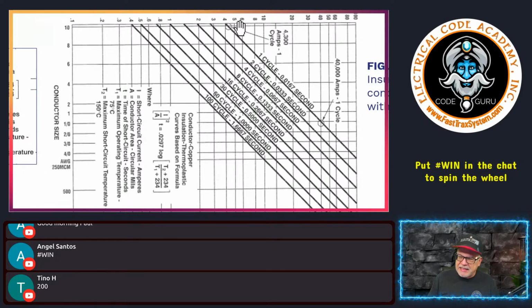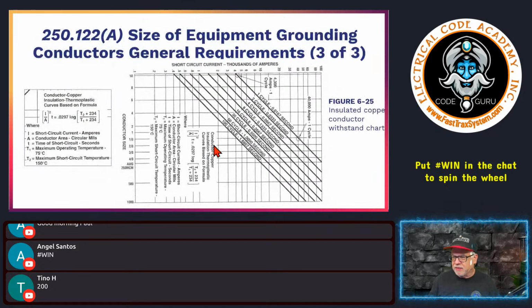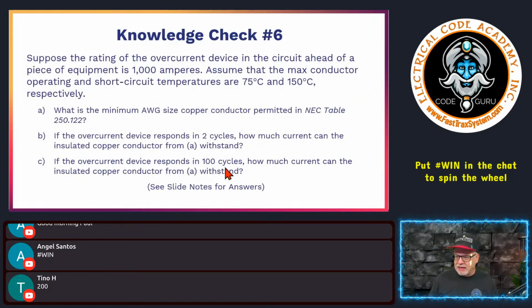That's dramatically different than when we saw it at 1 cycle or 2 cycles, which is in the 30,000 and up, right? That's how much that conductor can handle. And you can see that a lot has to do with the clearing time. The quicker the clearing, the more it can handle, because it's a very short duration. See what I'm saying? All right, so let's go back to the lesson. I got to bring this back down. You won't be able to see squat. All right, so that's where we got this.